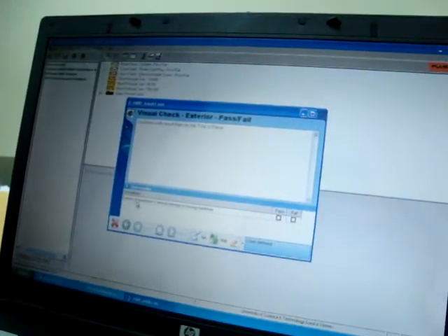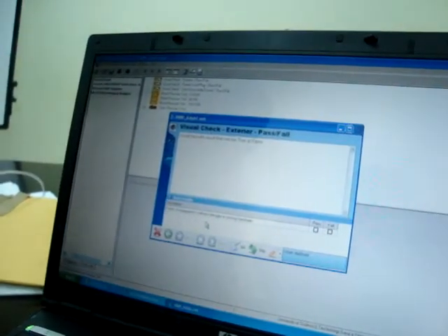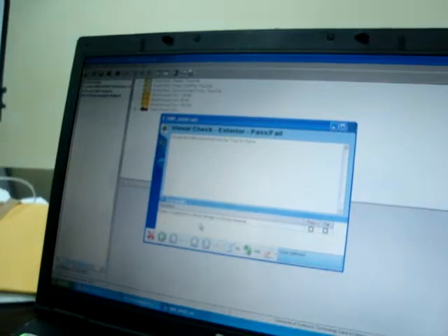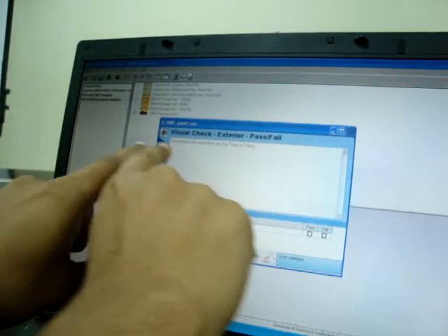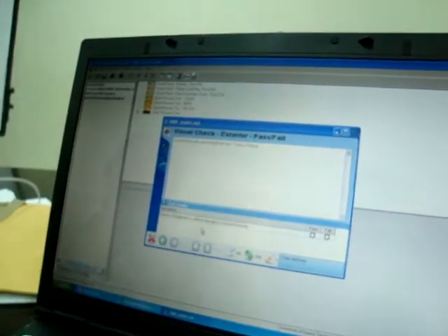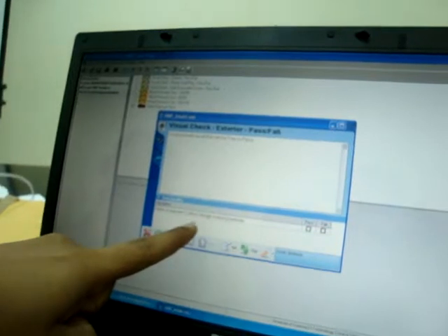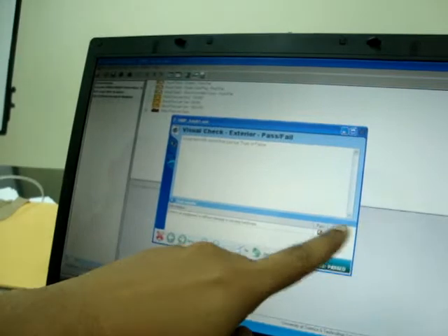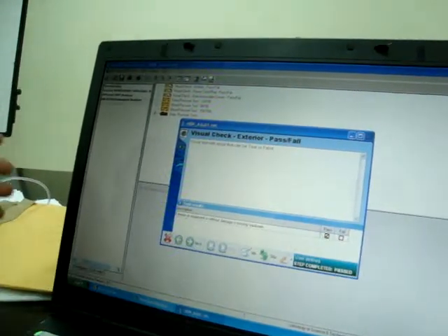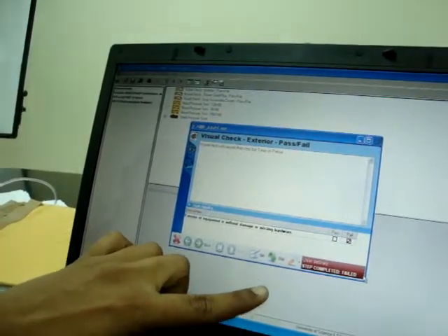Okay. See, exterior. This is for the PPM, preventive maintenance. This is like you are doing your routine. Or if someone new comes in your company, he doesn't know how to use it. You can type here whatever is needed. You can write in your own words, like check this equipment, how many cables, what is the limit. All this we can include. Okay. Is the exterior of the equipment without damage or missing hardware? Pass, yes or no. We can put yes or no also. Now pass. Or if we put fail, if not present, this step is completed as failed.